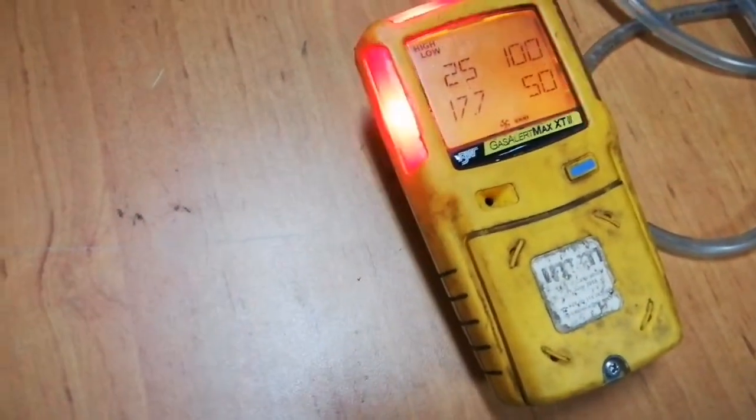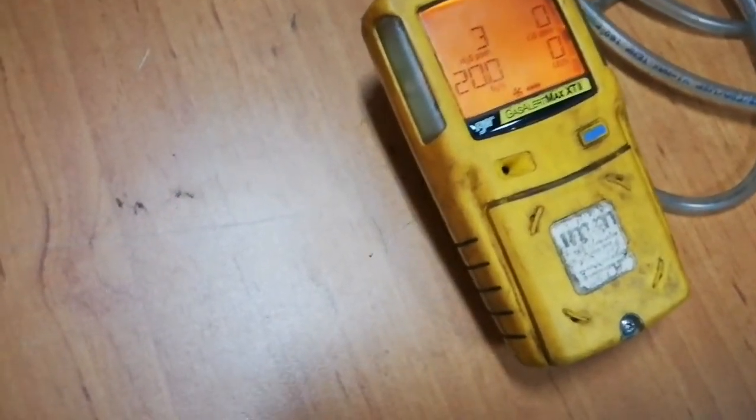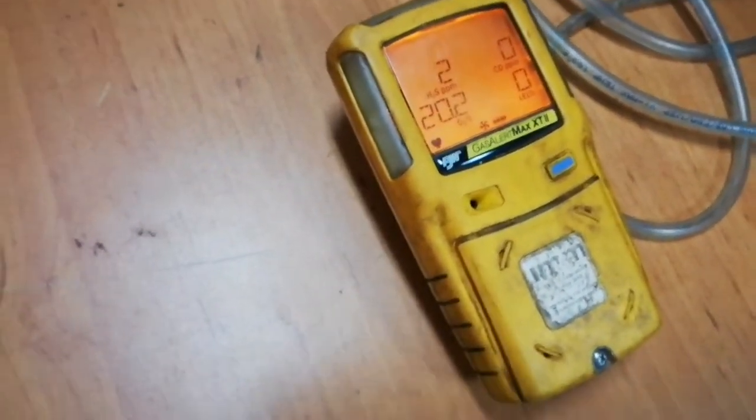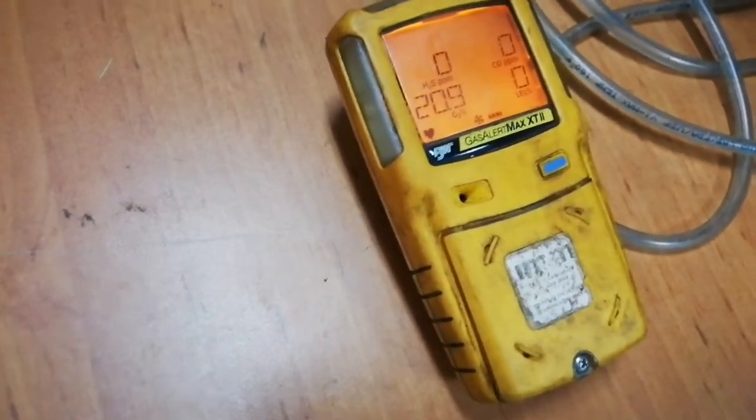Now we have to check the present atmosphere condition. Slowly the figures will be reduced. Here you can see H2S becomes zero, carbon monoxide becomes zero, and LEL becomes zero. Only oxygen is showing 20.9.